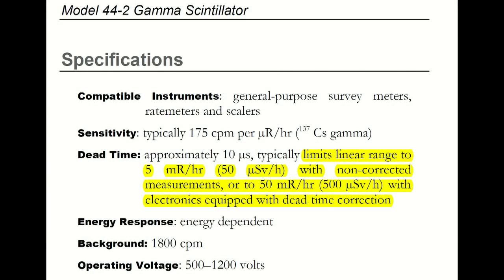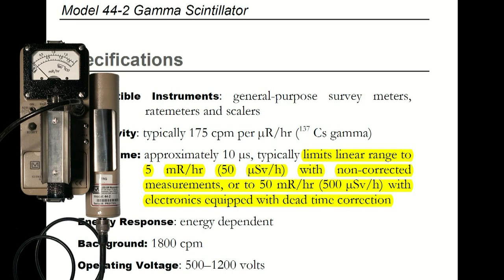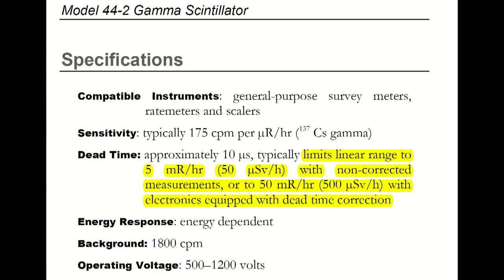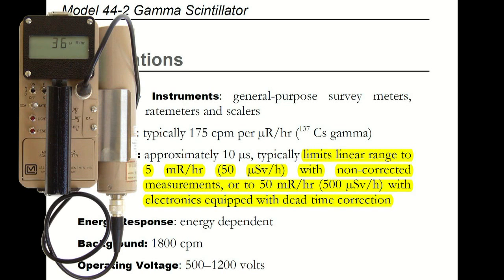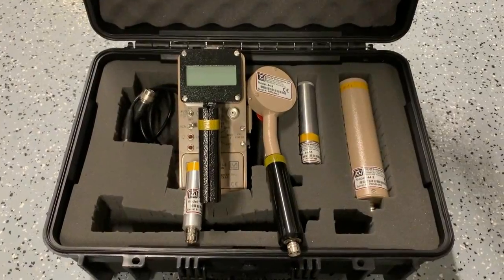If we look at the manual for the model 44-2 gamma scintillator on page 3, it talks about dead time. And it says that the dead time typically limits linear range to 5 mR per hour with non-corrected measurements. And that means with an analog rate meter like the Ludlum model 3 or the model 14c. But it can go up to 50 mR per hour if we have electronics that are equipped with dead time correction. That would be most of your rate meters that we see in these Ludlum response kits, like the model 2241 series rate meters.